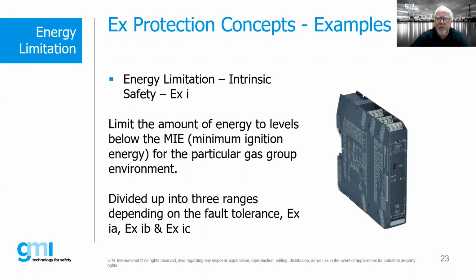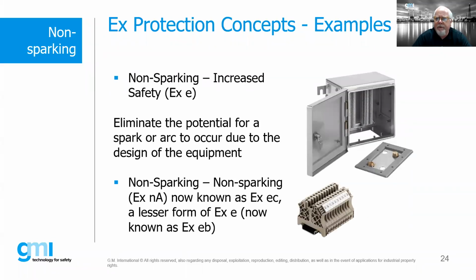Again, energy limitation. Now, increased safety is a concept that's been around quite some time. It was developed by the Germans. And this concept is basically saying, look, if we don't have any arcing or sparking going on inside of our enclosure, we eliminate that due to the design criteria of the terminals or whatever it is on the inside. Therefore, the enclosure does not need to be either flame-proof or pressurized or anything like that. So this is a very common protection concept that's used, especially for termination boards and junction boxes.